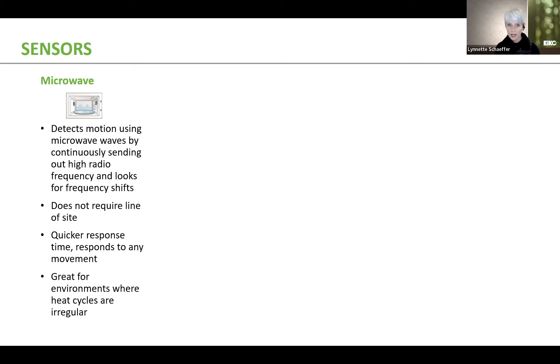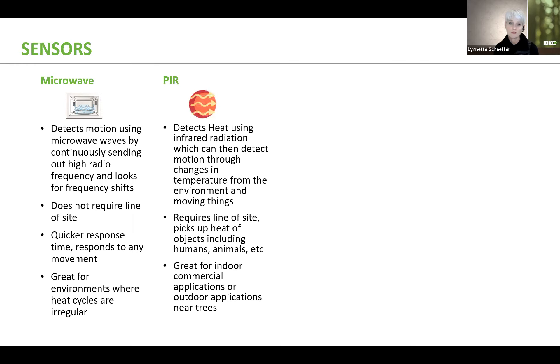Very much unlike PIR. PIR detects heat using infrared radiation, which can then detect motion through changes in temperature from the environment and moving things. This does require line of sight. So think of the matrix where you have red lines coming out of the sensor. If that red line is broken, then there's something going on and the sensor is going to react appropriately. Again, it requires line of sight. It picks up heat of objects, including humans and animals. It is really great for indoor commercial applications or outdoor applications near trees.